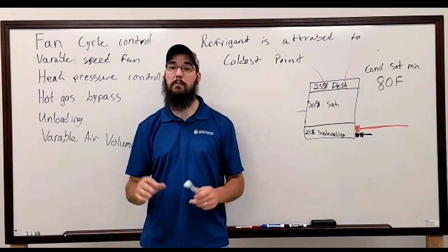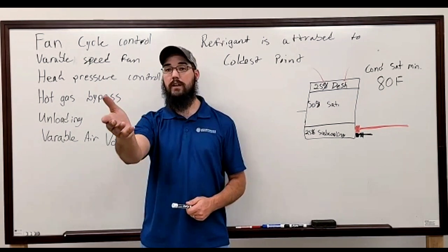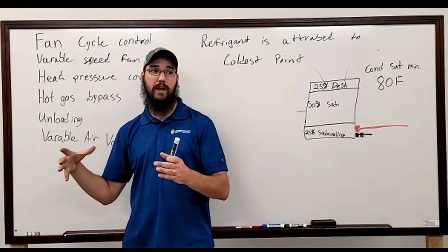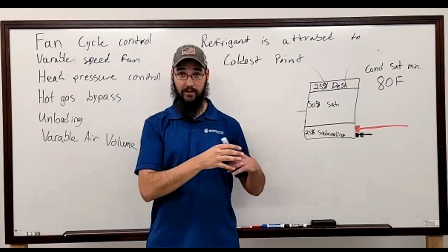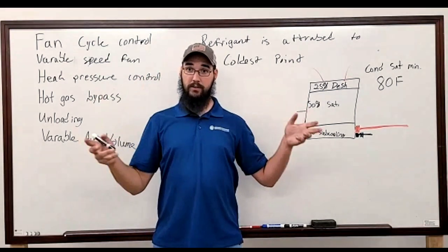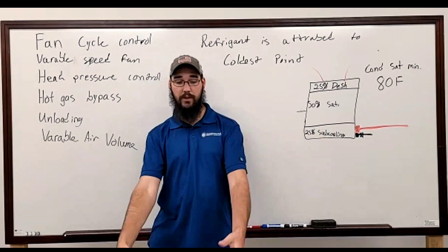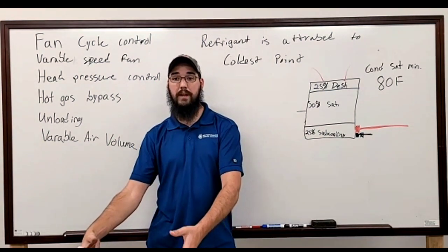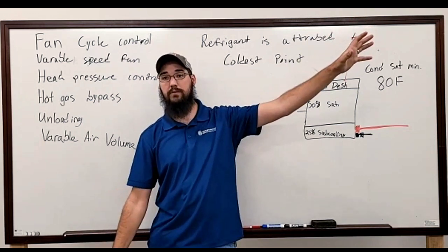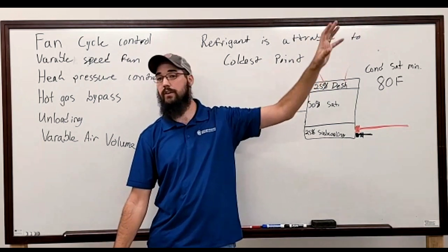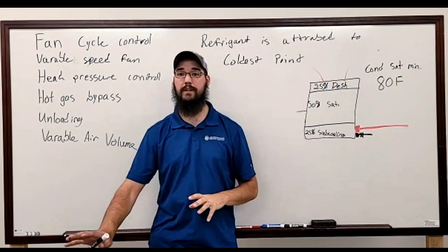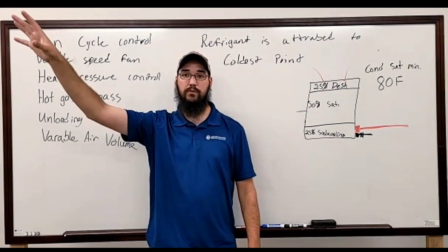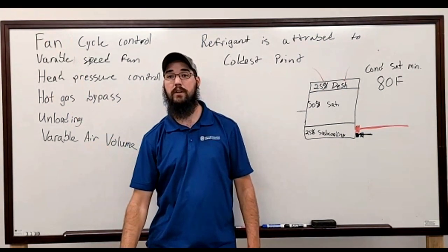The vast majority of them are on micro drives. The Daikin packs, as they call them. Those are not the Rebel series, where they have ECM motors. The Daikin packs, which are their spinoff of IntelliPAC, are in that little refrigerant compartment down below. That is strictly running off of the MicroTech 3 controller. It's being told everything it needs to do from that controller. It's not independent. But those are just standard condenser fan motors being run off of a drive.